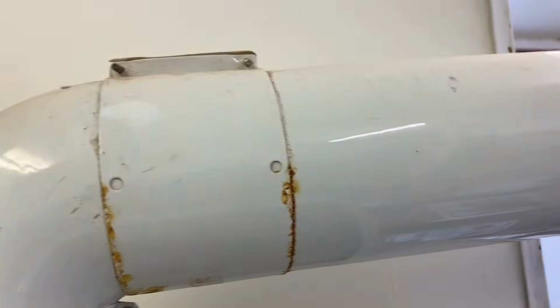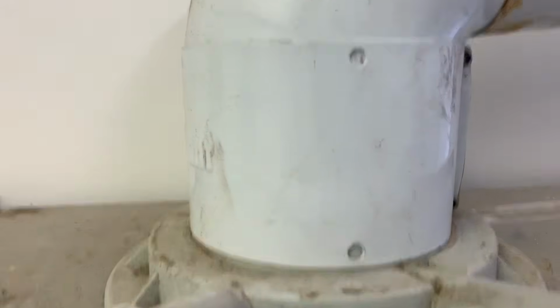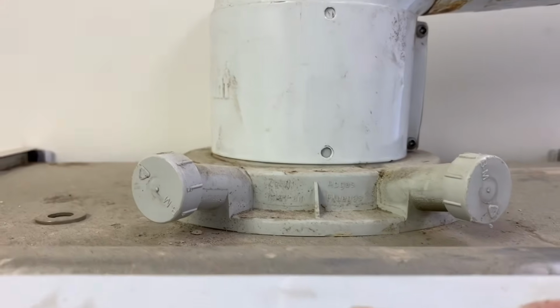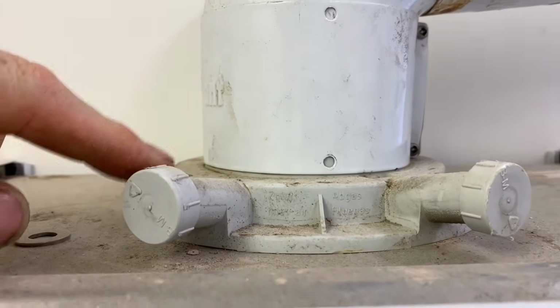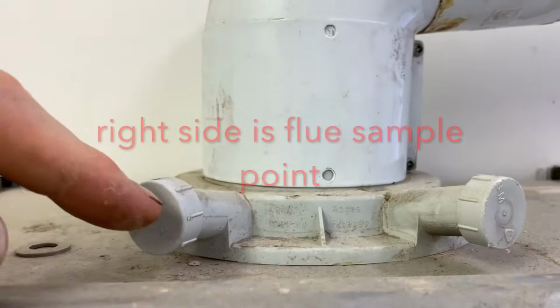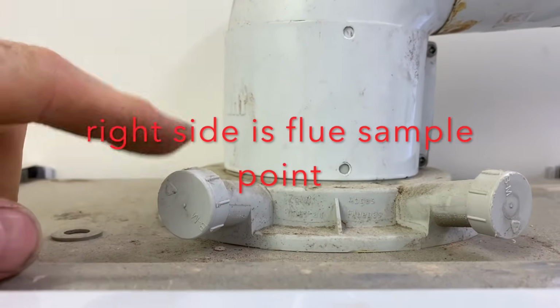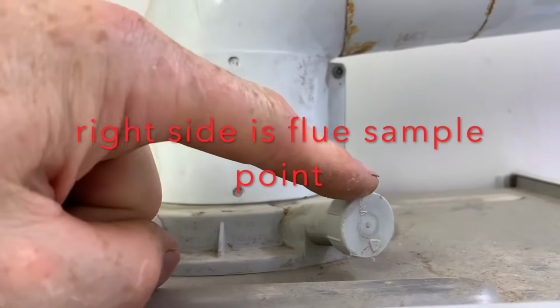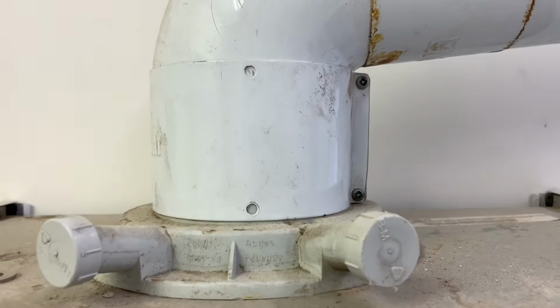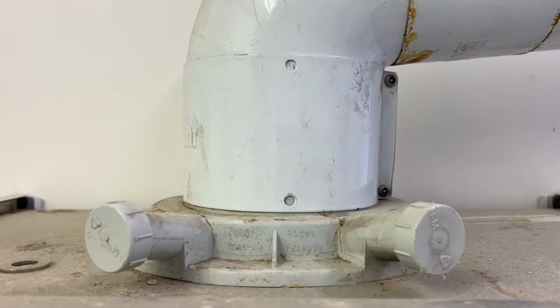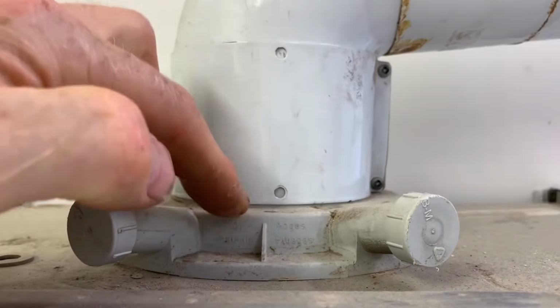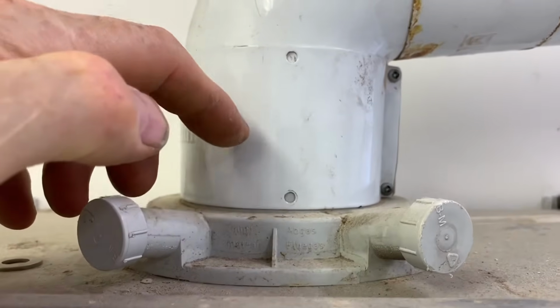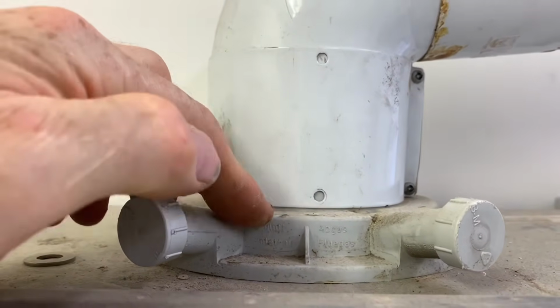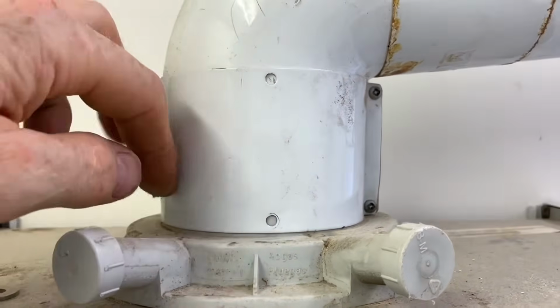So this is the flue at the top of the boiler, and this is the flue turret. So these are our sample points. If I remember correctly, this is our flue gas analysing, and this is our flue integrity testing. So this is where we would do our test. Now I quite like the design of the turret on this one because you can connect vertical or horizontal on it by just using a clamp.